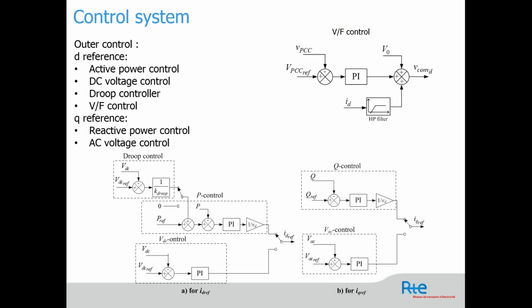For the outer control, of course, you have several types. For the D reference, you have the choice between active power control, DC voltage control, droop control, and VF control. So let's start with the P control. It is shown here. In the P control, you have a loop to set up the active power reference when the station is set as a P control.